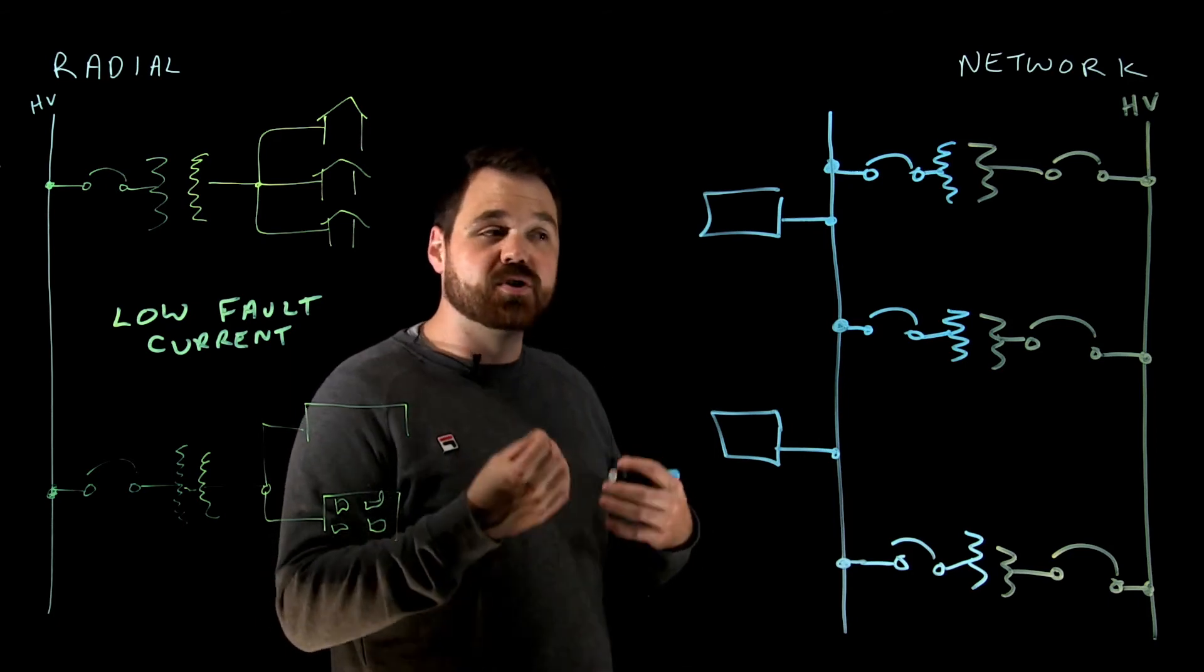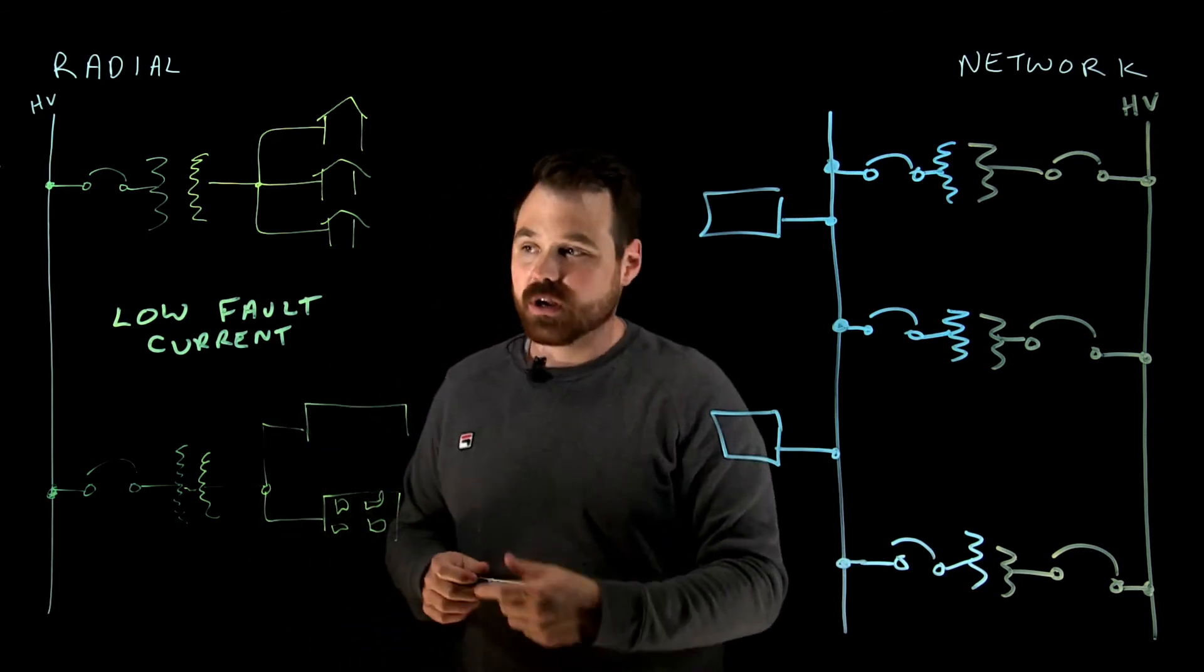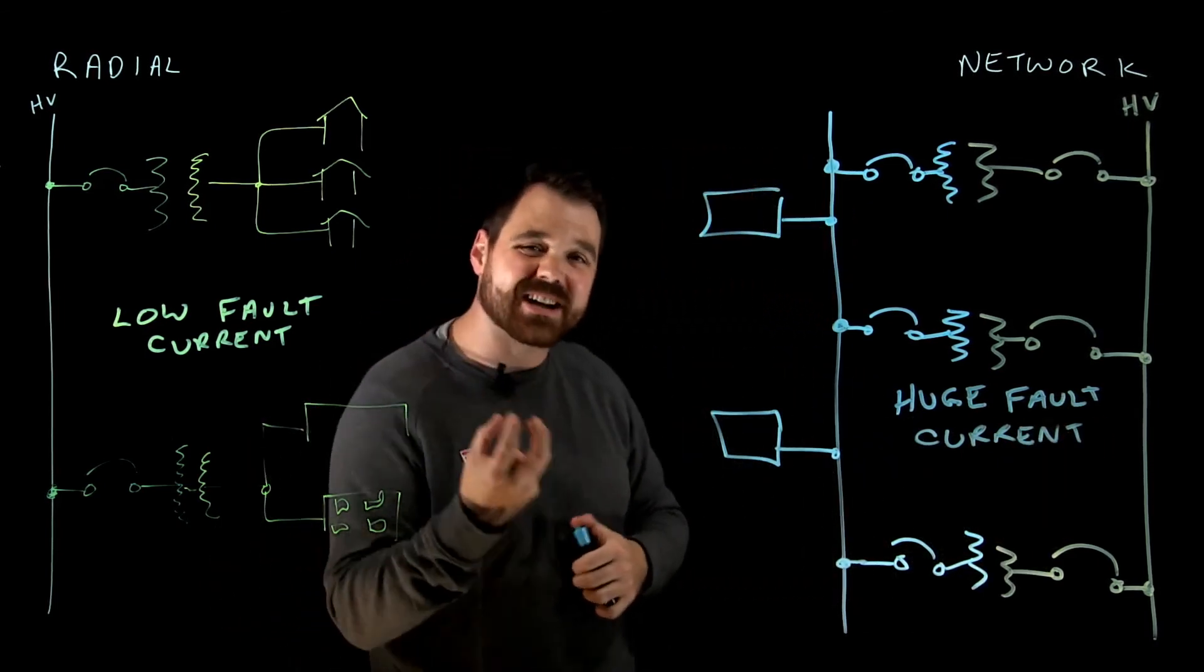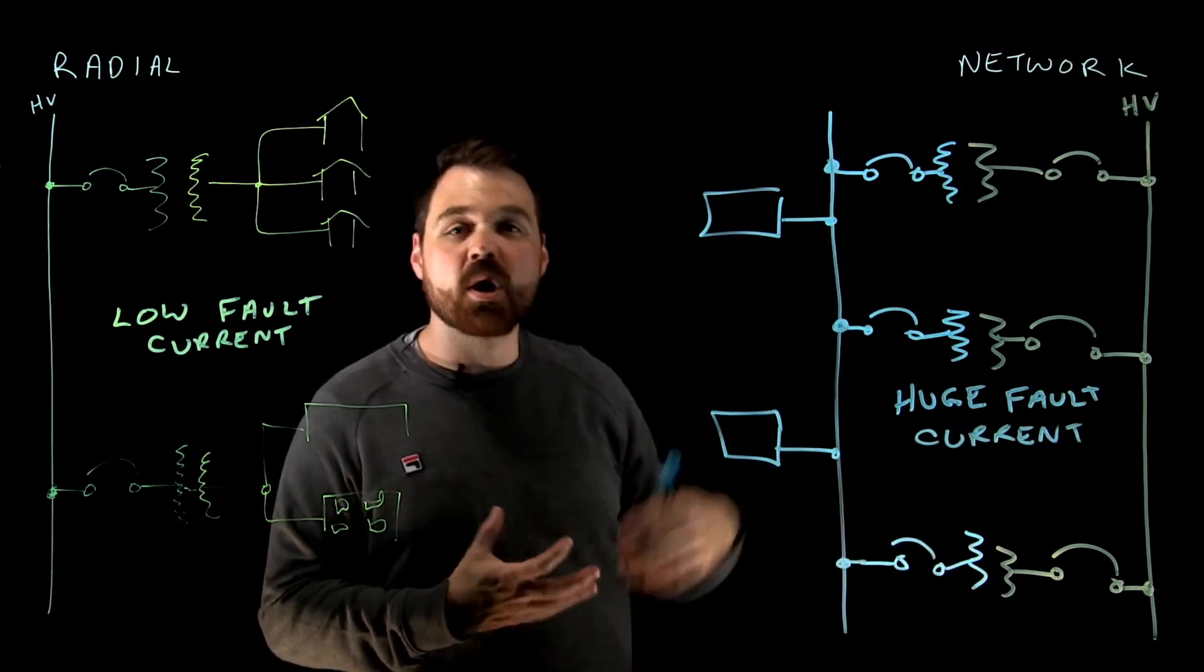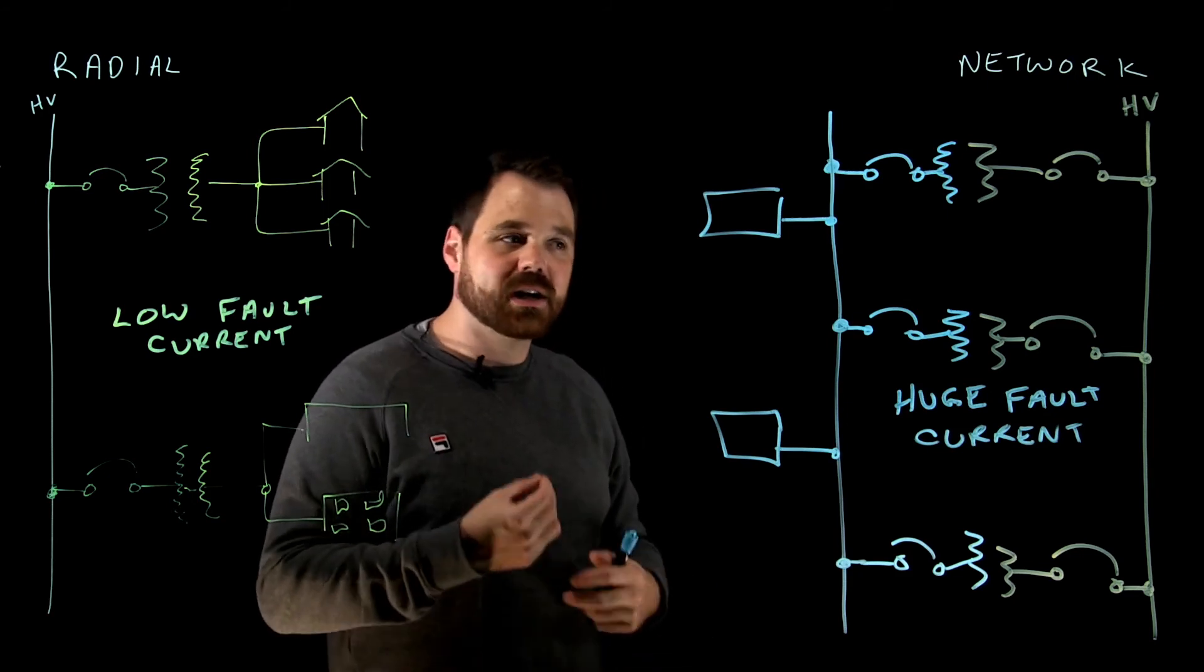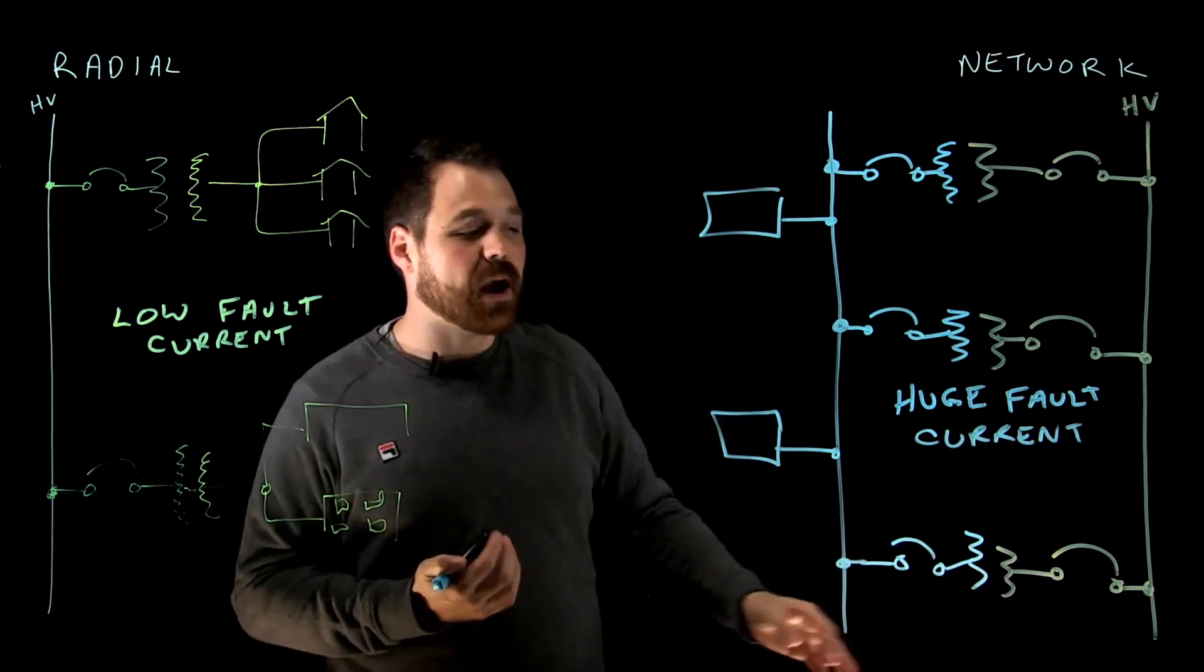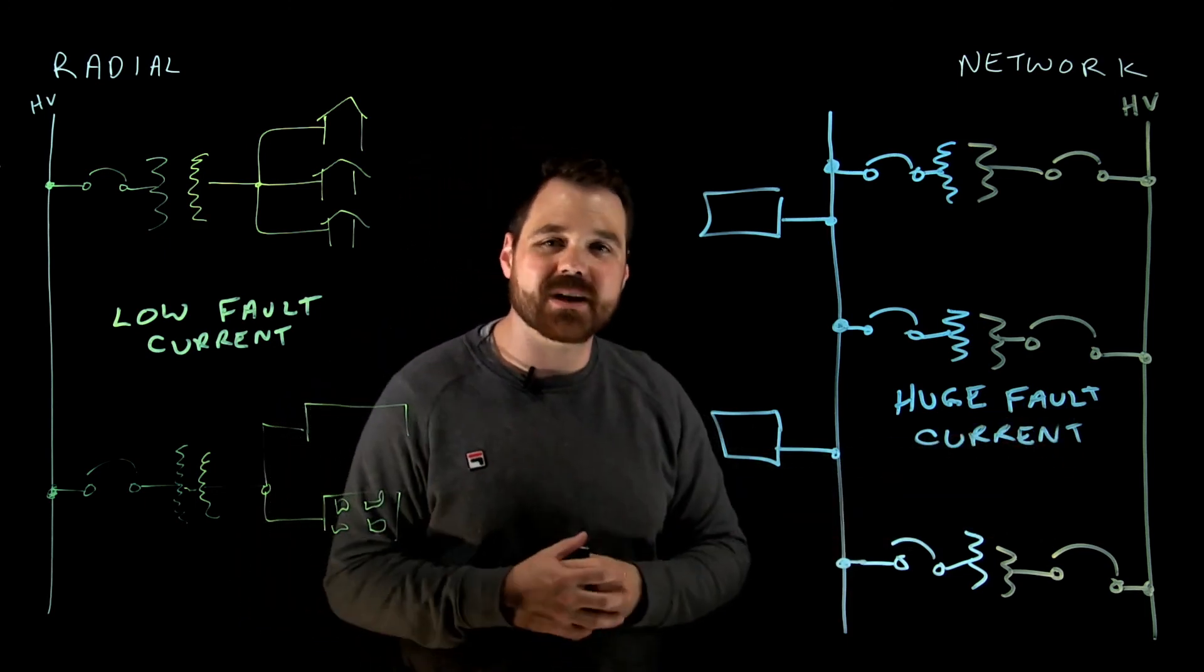However, that can provide a few problems. Because we have that big available KVA, now what could happen is we could have a huge fault current. So we need to be careful with this when we are sizing our protection devices, they often need a higher interrupting rating, because they need to be able to interrupt the fault current of multiple transformers. So it is really something that you need to work with your supply authority or your utility provider with. And sometimes this can even be a closed loop where they come back around in a circle, and that would be kind of called a ring system. But either way, it's all that network system, huge available KVA, a little bit more reliable. But we deal with bigger fault currents that we need to think about.